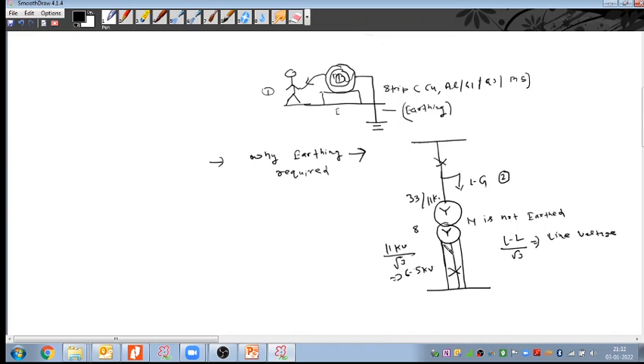Then what will happen? Since the equipment's phase insulation is designed for the phase voltage, if the voltage at the event of the fault jumps to the line voltage, then this insulation will break down due to the higher voltage, that is, the line voltage. I mean to say, if I have designed the insulation for 6.5 kilovolts, and 11 kilovolts is coming on it, then we could not sense the fault. Second, the equipment is going to fail, the insulation is going to fail due to the higher voltage stress.